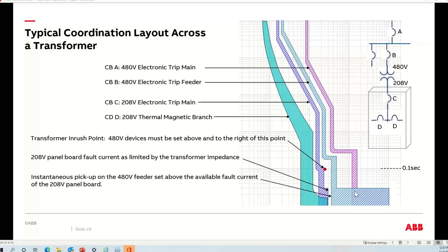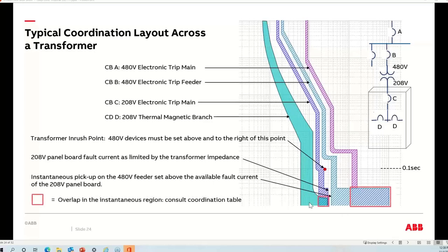Getting to this point, the only decisions left are: how do I know the areas of overlap coordinate? That's where the vendor coordination table ensures you have the correct breaker pairs and guides you on any special settings requirements to confirm that overlap is in fact coordinated.